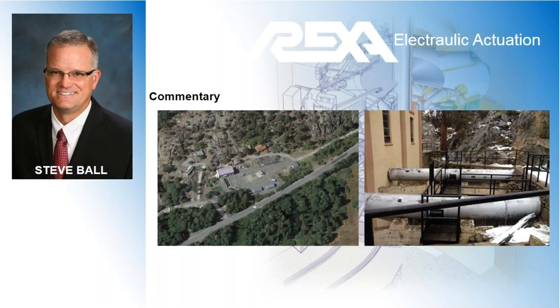The turbine itself, which is on a base rating of 8,000 horsepower, was due to be replaced with a modern stainless steel turbine. And at the time, it was seen that this would be a good opportunity to look into upgrading its governing system. Now, where we use REXA here wasn't specifically for governing, but it has some very key features that we added to the plant by utilizing REXA as a needle control that gave this plant something it never historically had.